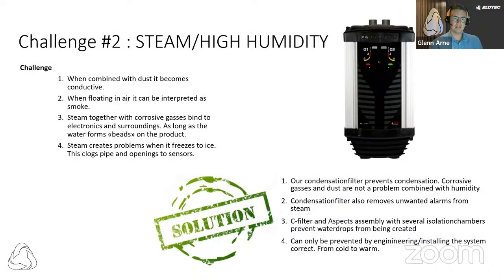Another challenge can be steam and high humidity, especially in the Dubai area where you have very high humidity in the air. And what is really the challenge? When combined with dust, it becomes conductive. When floating in air, it can be interpreted as smoke. Steam together with corrosive gases binds to electronics and surroundings, as long as the water forms beads on the product.